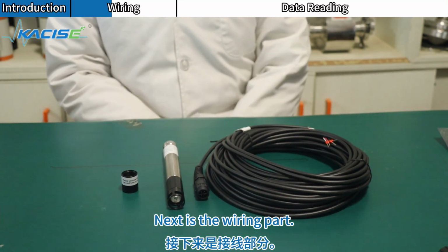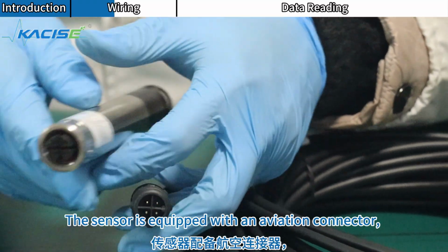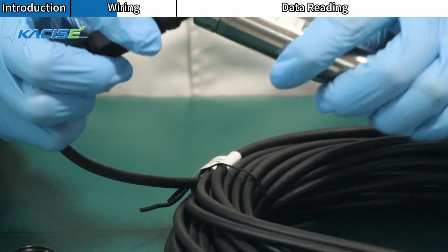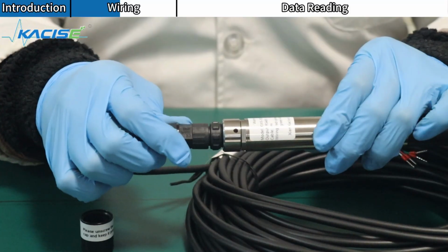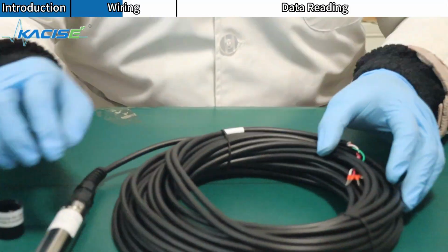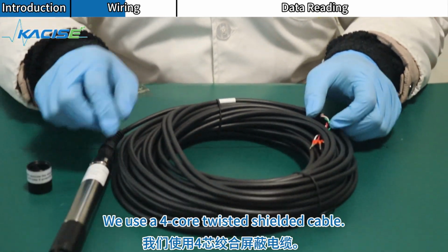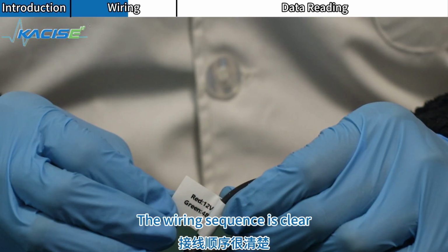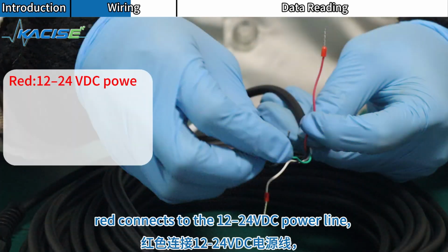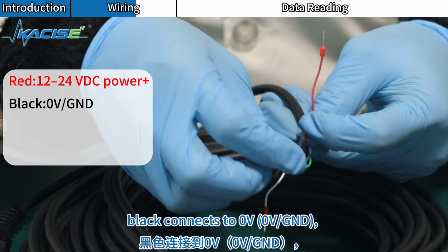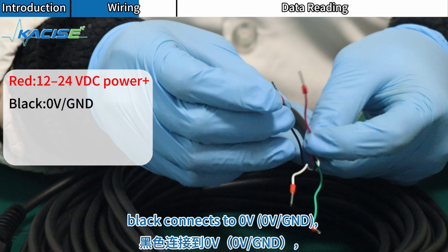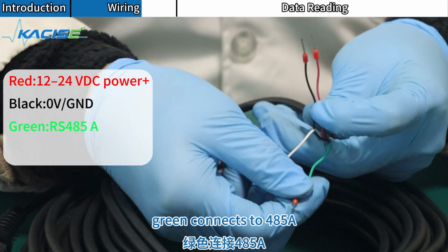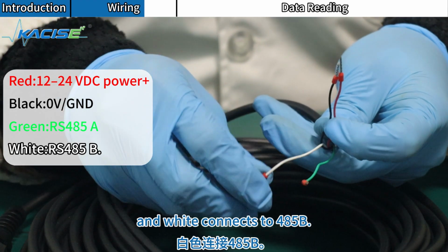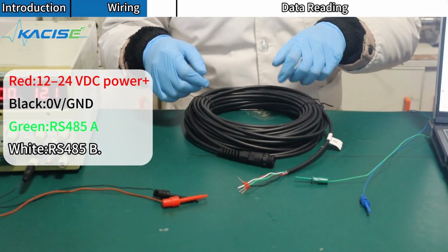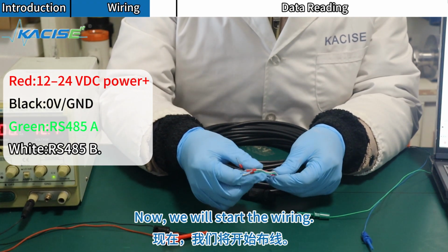Next is the wiring part. The sensor is equipped with an aviation connector. We use a 4-core twisted shielded cable. The wiring sequence is clear. Red connects to the 12 to 24 VDC power line. Black connects to 0 volts, GND. Green connects to 485A, and white connects to 485B. Now, we will start the wiring.